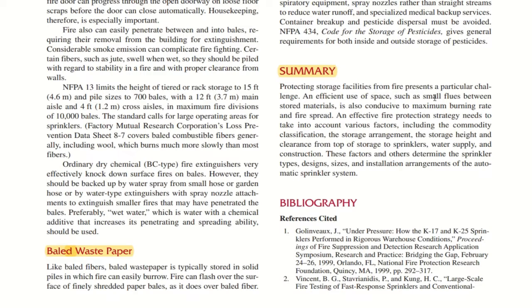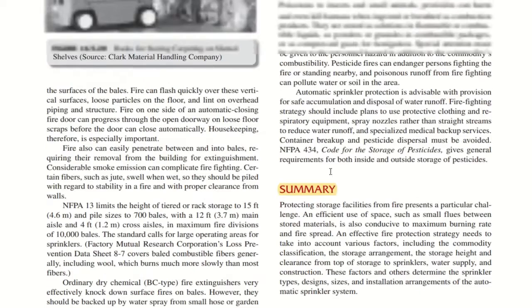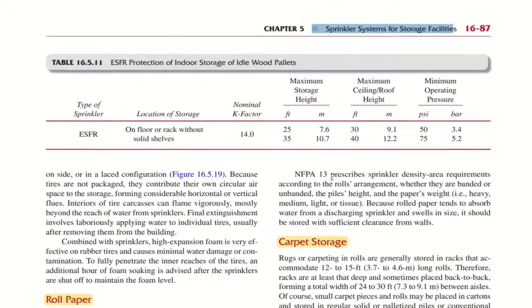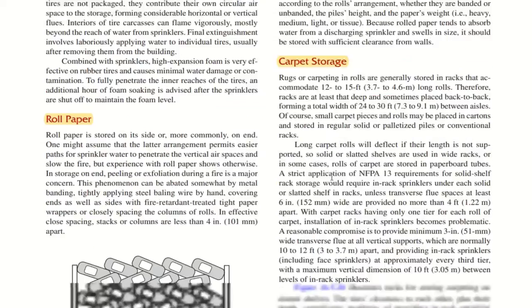Protecting storage facilities from fire presents a particular challenge. An efficient use of space, such as small flues between stored materials, is also conducive to maximum burning rate and fire spread. An effective fire protection strategy needs to take into account various factors including the commodity classification, the storage arrangement, the storage height, and the clearance from top of storage to sprinklers, water supply, and construction. These factors and others determine the sprinkler types, designs, sizes, and installation arrangements of the automatic sprinkler systems. Basically this chapter 5 refers to sprinkler systems for storage facilities.